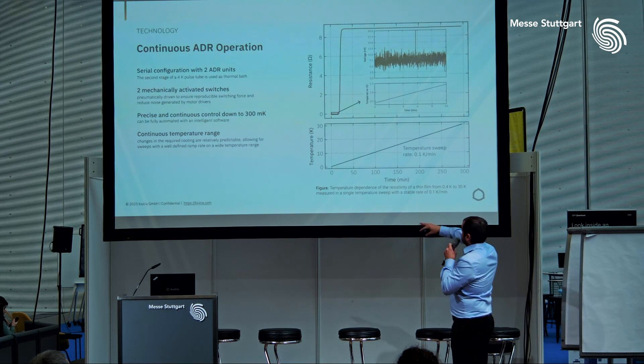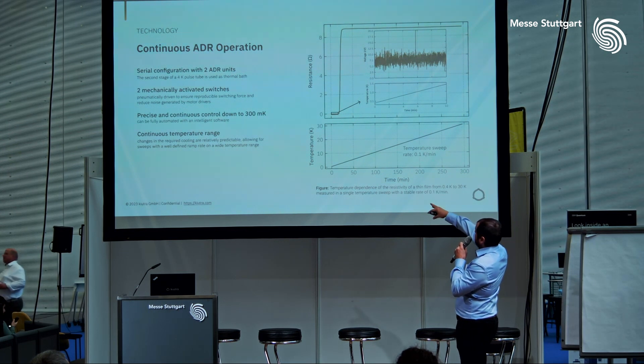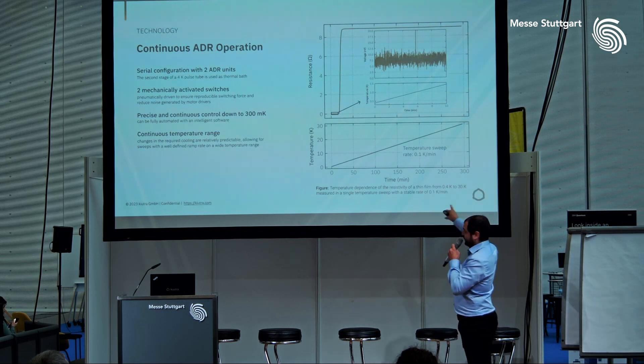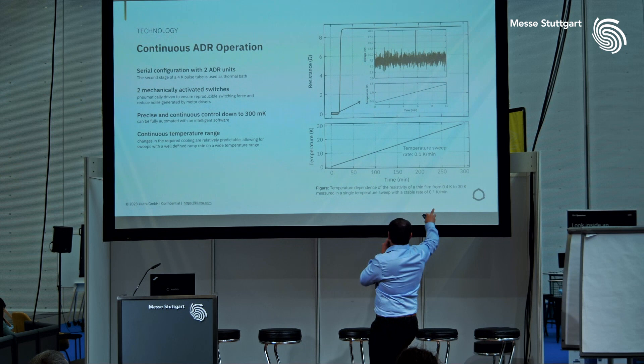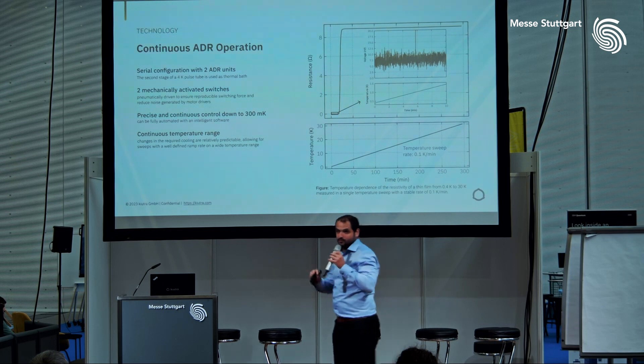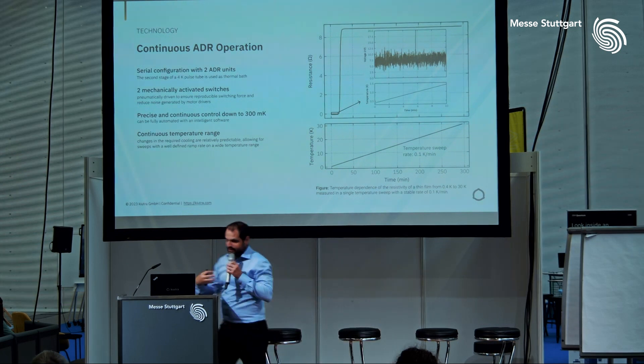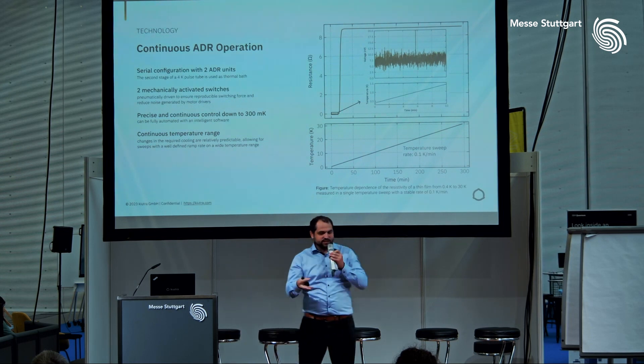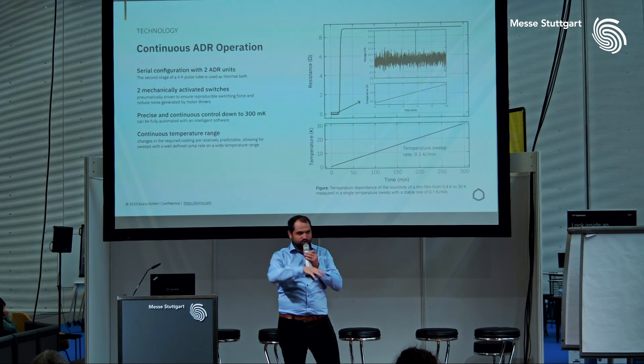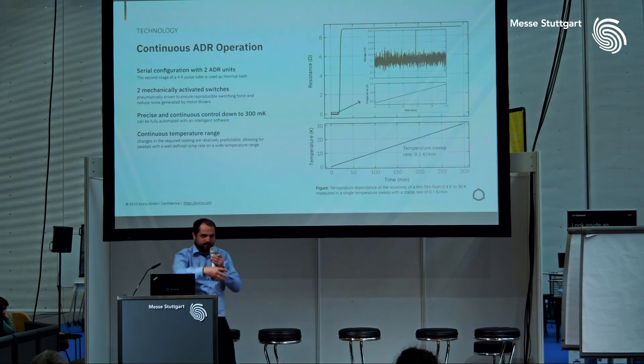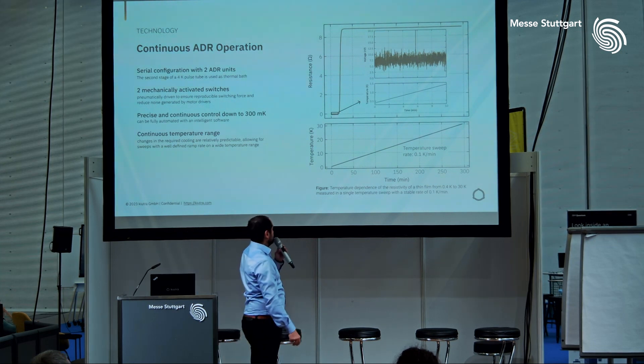Here for instance we have a very low-noise measurement of the resistivity of a sample — we can see a superconducting transition — plotted over time. This was done over 300 minutes with a ramp rate of 100 mK per minute, so a very well-controlled ramp rate. The intelligent software switches automatically from ADR control to cryocooler and heater in the background, all taken care of by the software.